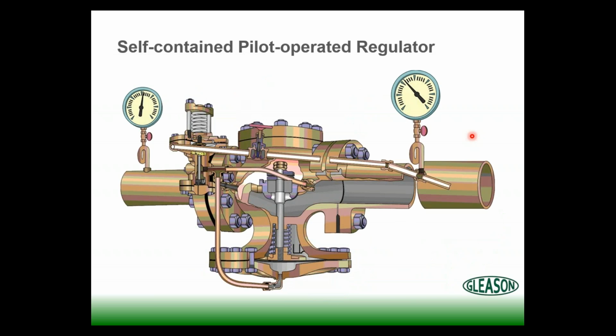A couple more things, then we'll go to questions, so hang in there with me. Many of you have pilot-operated regulators. Notice this control line. We see this all the time. It should slope down and away from the pilot. Many folks will come up and then down. We don't want any condensate being held up against the pilot right there, because it will affect the accuracy of regulation.